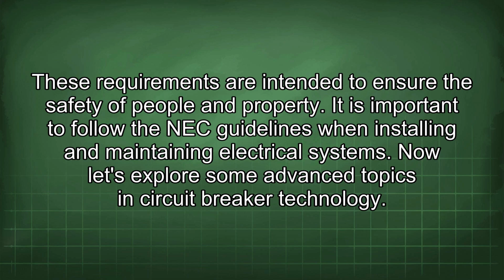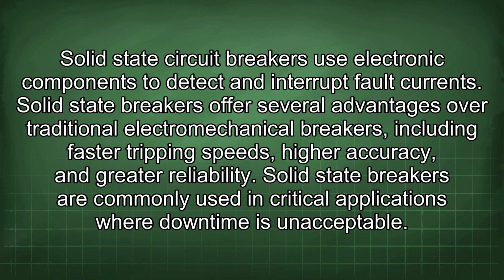Now let's explore some advanced topics in circuit breaker technology. Solid-state circuit breakers use electronic components to detect and interrupt fault currents. Solid-state breakers offer several advantages over traditional electromechanical breakers, including faster tripping speeds, higher accuracy, and greater reliability. Solid-state breakers are commonly used in critical applications where downtime is unacceptable.